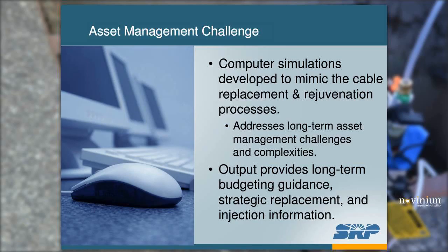And the way we did this at SRP is we developed some computer simulations that essentially mimic our cable replacement and rejuvenation processes. And we take the output from these simulations to give us some budgeting guidance. It helps us perhaps with some strategic replacements, and it allows us to monitor and evaluate our injection performance.